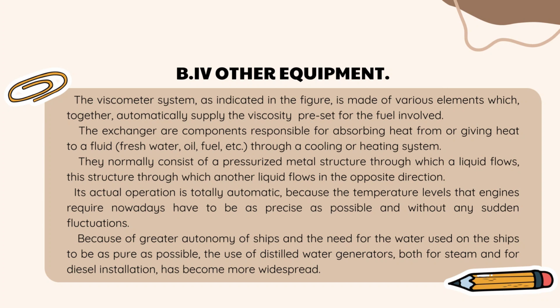The exchanger comprises the components responsible for absorbing heat from or giving heat to a fluid, fresh water, oil, fuel, etc., through a cooling or heating system. They normally consist of a pressurized metal structure through which a liquid flows, this structure through which another liquid flows in the opposite direction. Its actual operation is totally automatic, because the temperature levels that engines require nowadays have to be as precise as possible and without any sudden fluctuations.